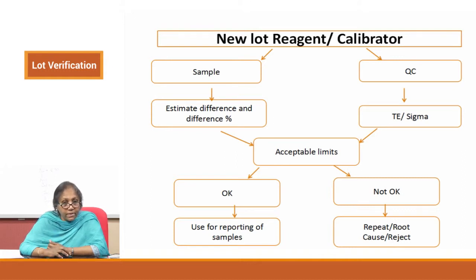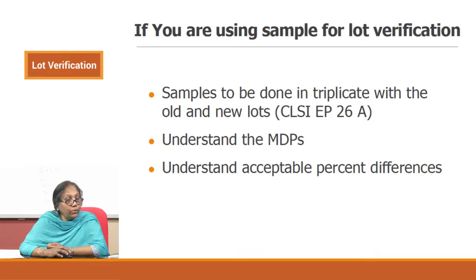In the case of using QC, you also have to specify your acceptability — what is your total error that you will accept and what is the sigma that you will accept for that reagent. If it is found acceptable, you put it into use; if not, you do the same — repeating or rejecting as the case may be. Let us examine how you will do both of these things.